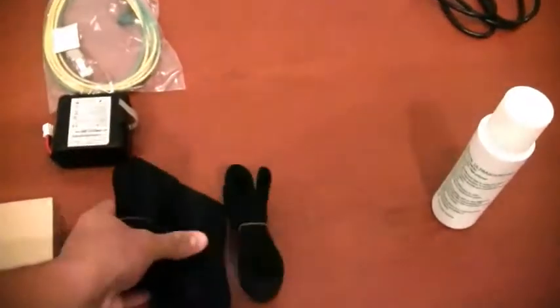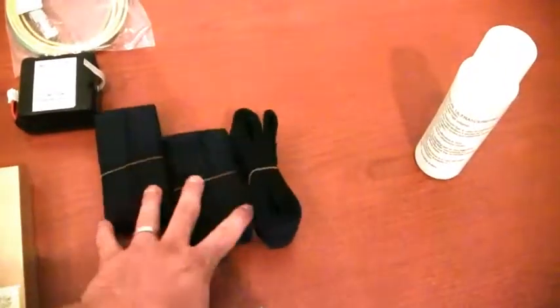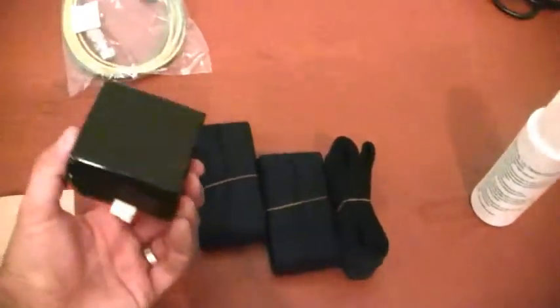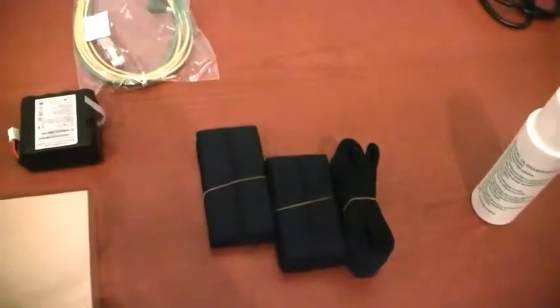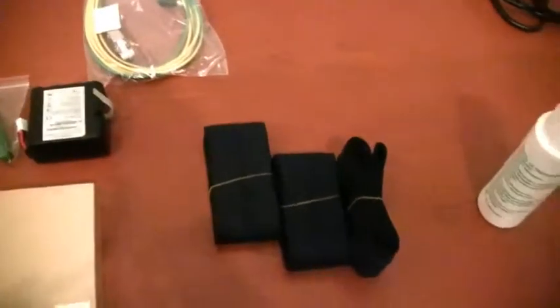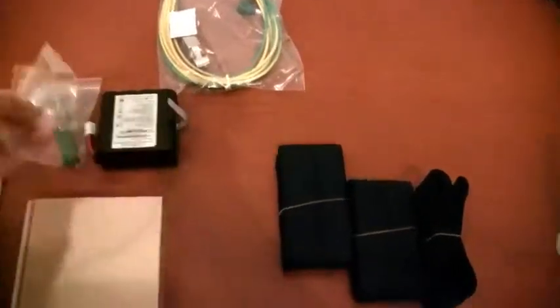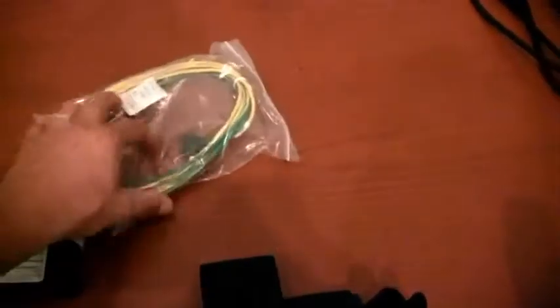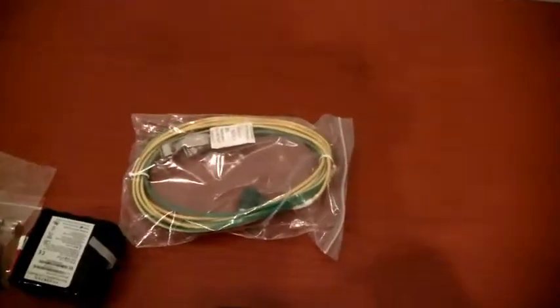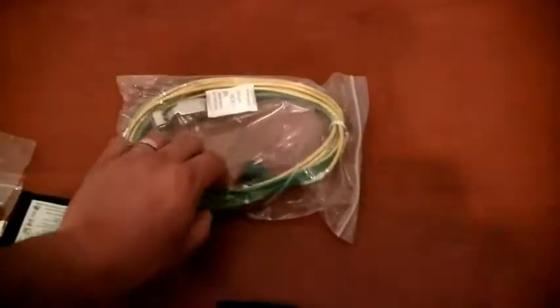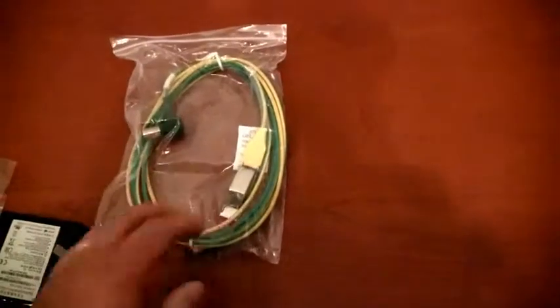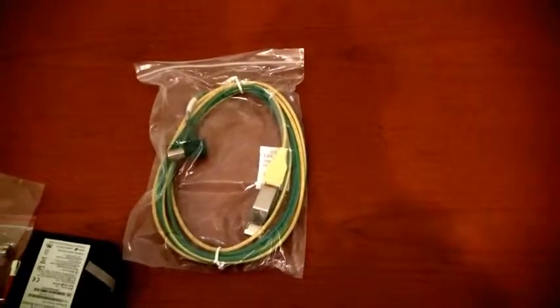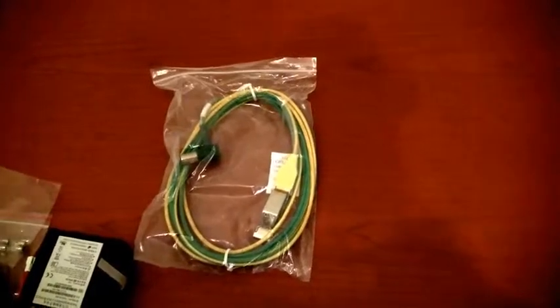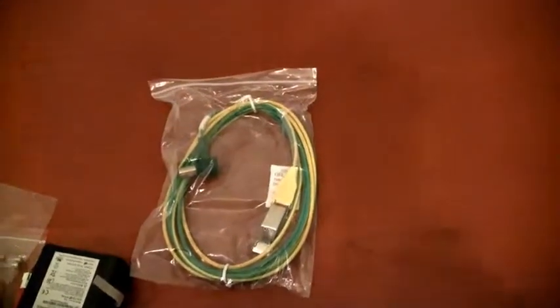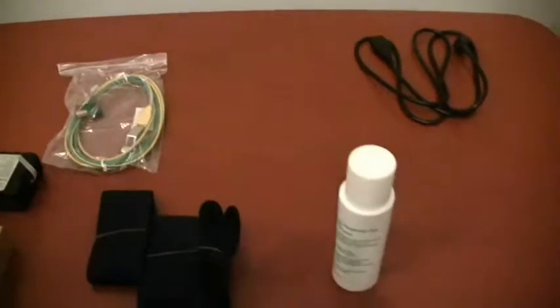Your fetal monitoring belts for your TOCO and your transducer. A battery as well. We can give you the screwdriver to install the battery in the back of the device. Some extra fuses in case one should happen to burn out. A ground cable, which typically doesn't apply in the United States, but if it's going overseas and there's a non-grounded electrical system, this would certainly come into play. It can also be used in the States if for some reason you're getting any kind of interference from other devices in the facility or in the room where the tests are being run.